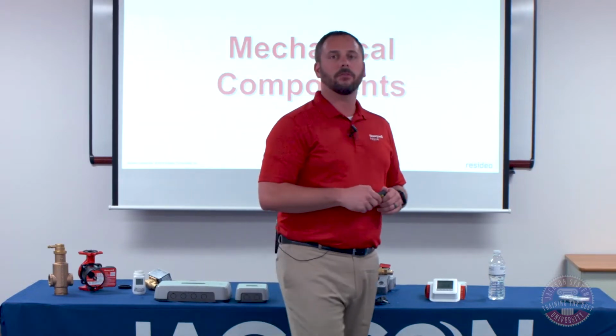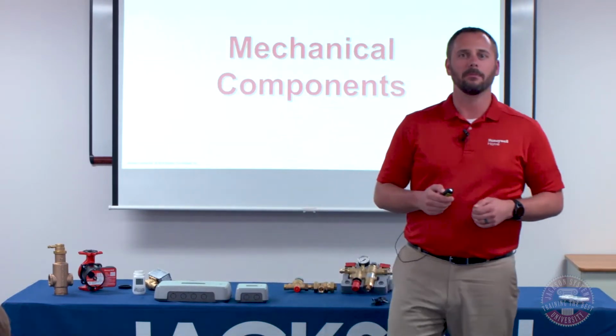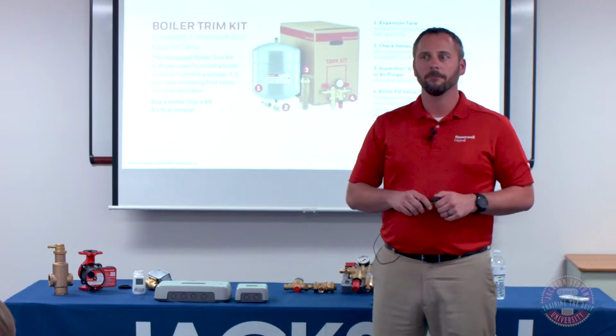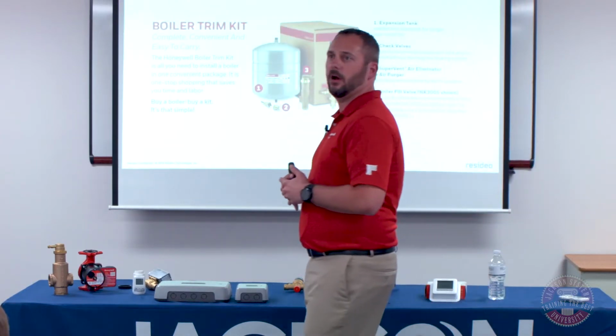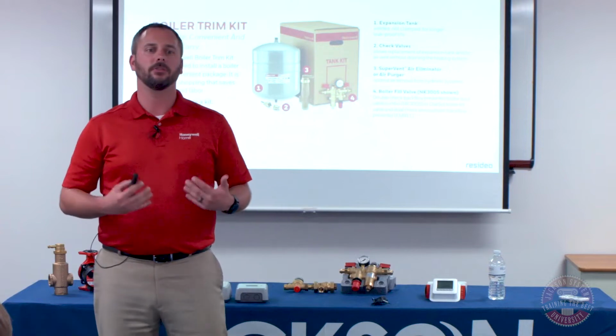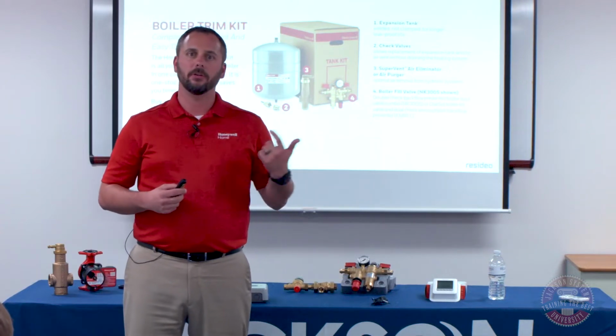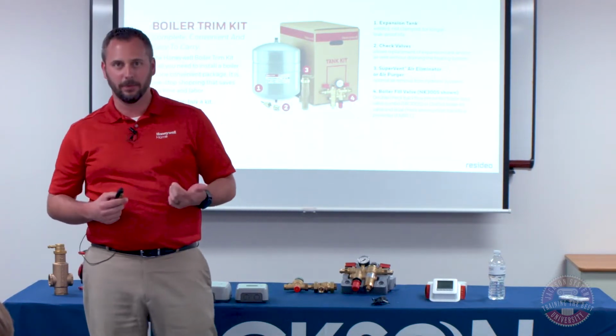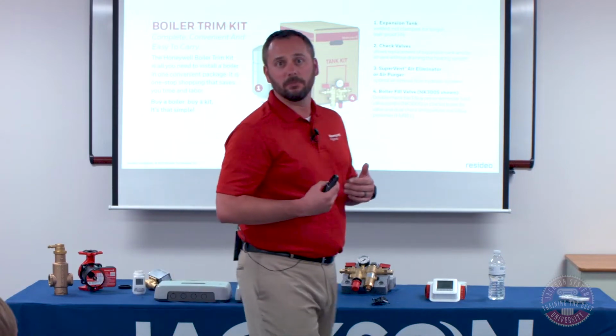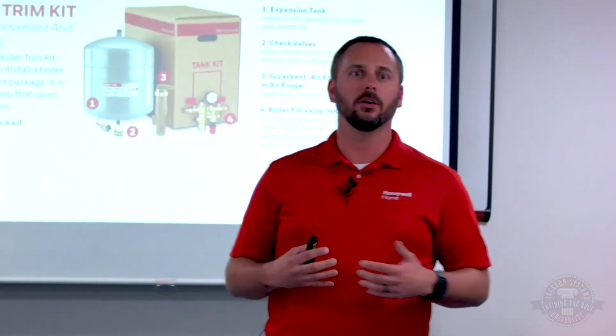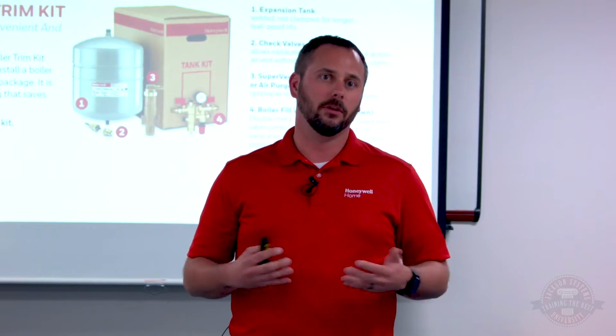To start off, I'm going to start with the mechanical room and then branch out into controls. One of the products that we have started doing is a packaged system with air eliminators, fill valves, backflows, and expansion tanks. We started doing this because this is needed in virtually every single hydronic heating system that's not filled with glycol.